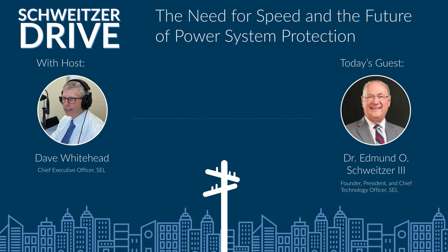So that's our first shot at it. And the information comes from the fault itself. Now, when we do short circuit studies in our traditional 60 hertz world, we think of a fault, and then the sources are going to push fault current through it. But that's not what really happens. The sources don't even have time to budge or move, or sometimes even see the fault, before we've got it all figured out.